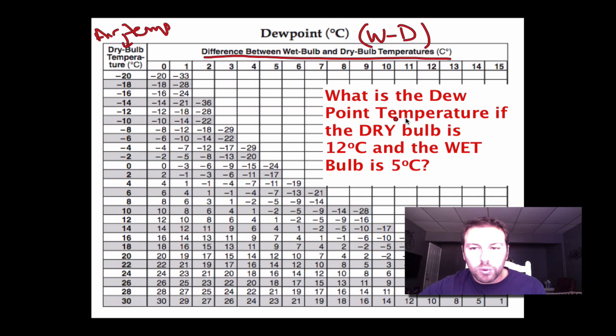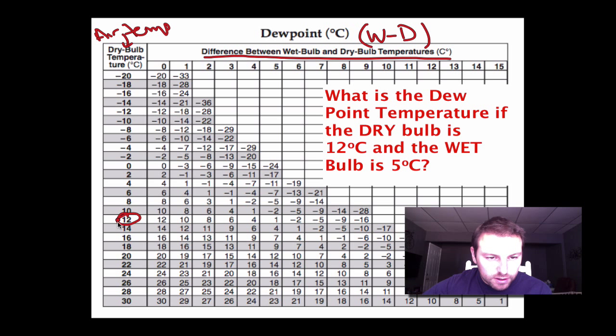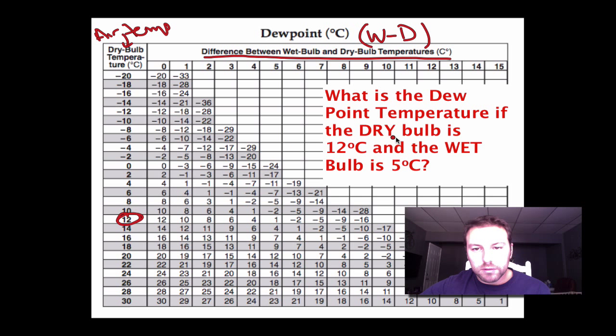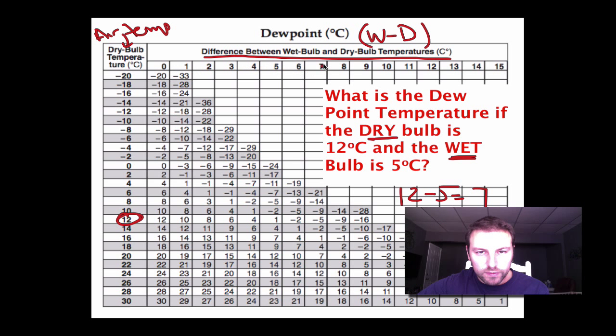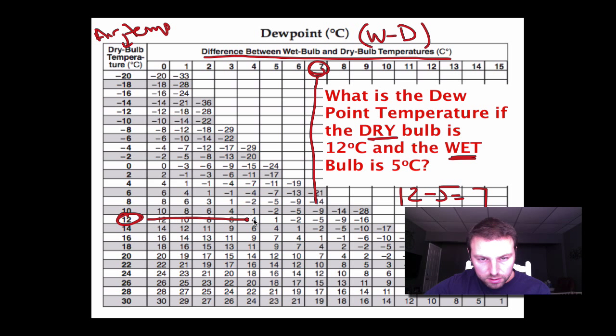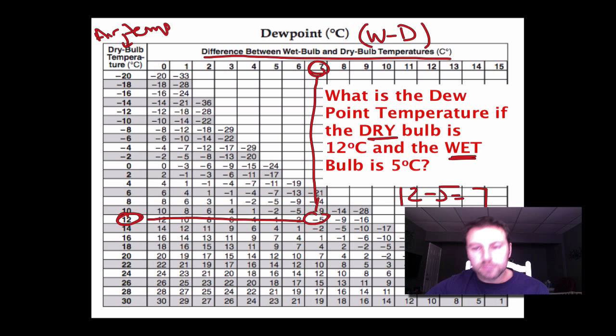In example B: what is the dew point temperature if the dry bulb is 12 degrees Celsius and the wet bulb is 5 degrees Celsius? First, go to the left side of the chart and find the dry bulb temperature — 12. Then find the difference between wet and dry bulb: 12 minus 5 equals 7. Go to the top of the chart and find 7. Where the two values meet is your dew point temperature — negative 5 degrees Celsius. Done, pretty easy.